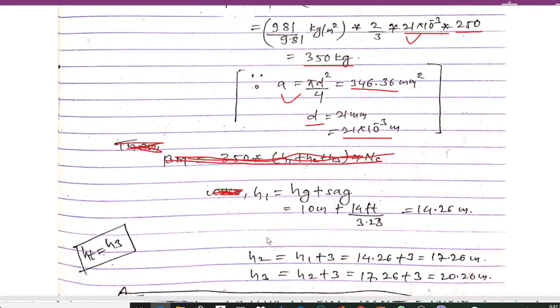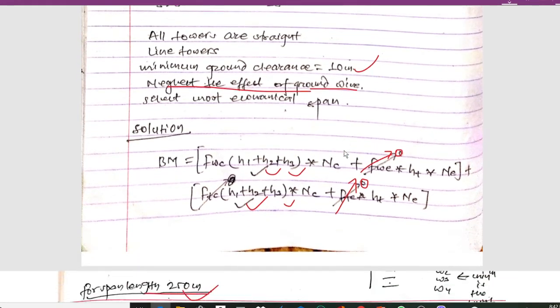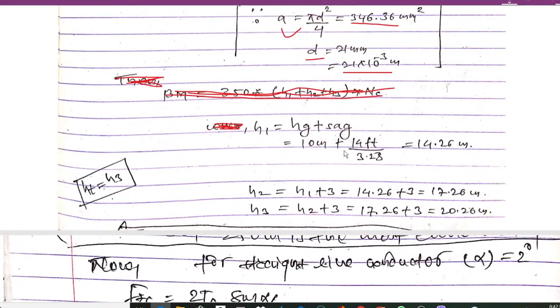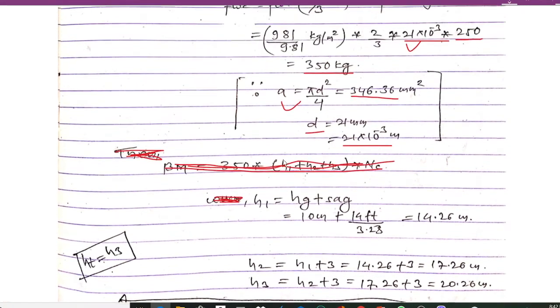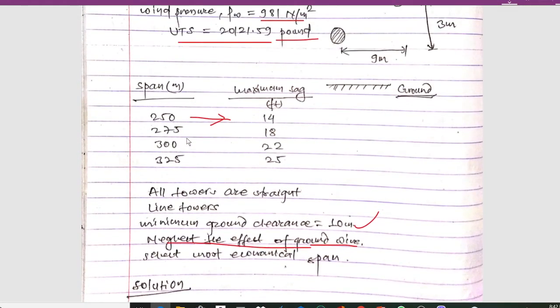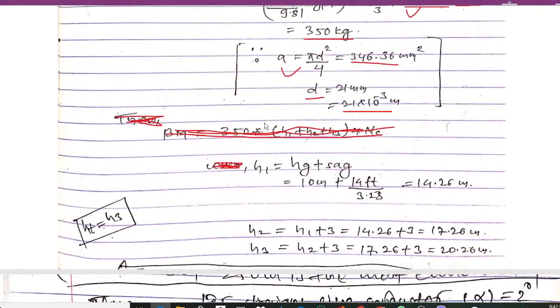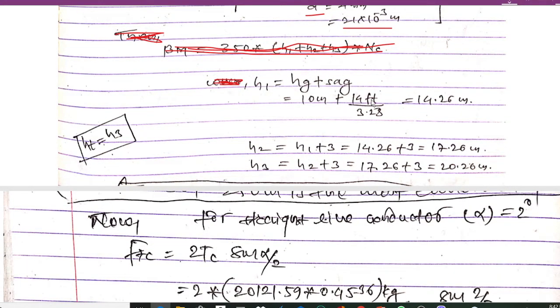Now we calculate S1, where S1 = SG + sag. SG is the minimum ground clearance = 10 meters. For the 250-meter span, the maximum sag from the table is 14 feet. Converting to meters by dividing by 3.28 gives approximately 4.26 meters. Therefore S1 = 10 + 4.26 = 14.26 meters. S2 = S1 + 3 = 17.26 meters, and S3 = S2 + 3.